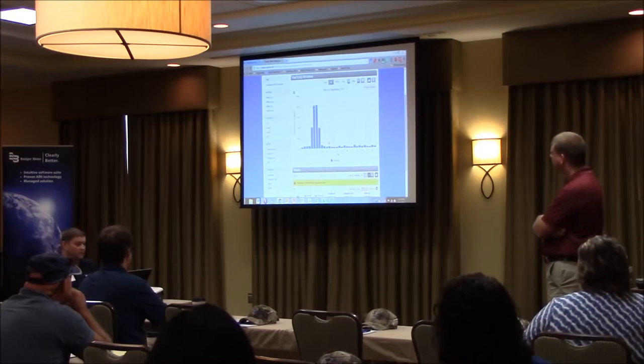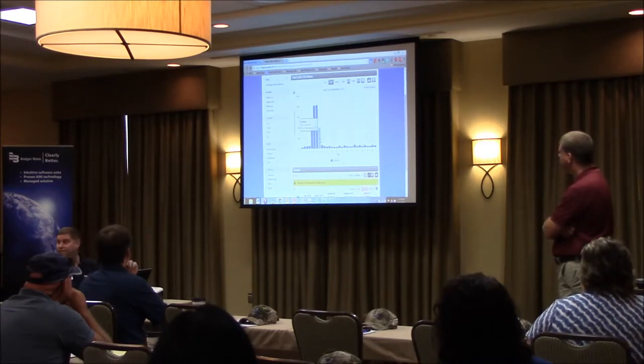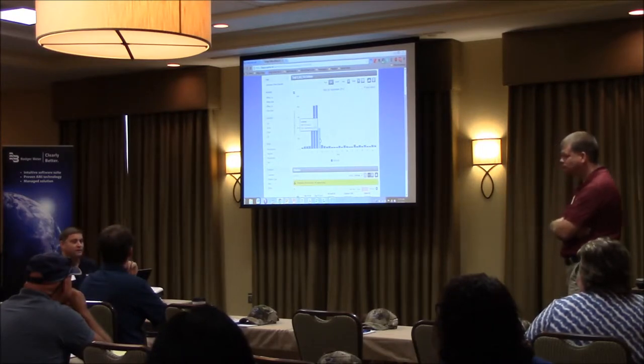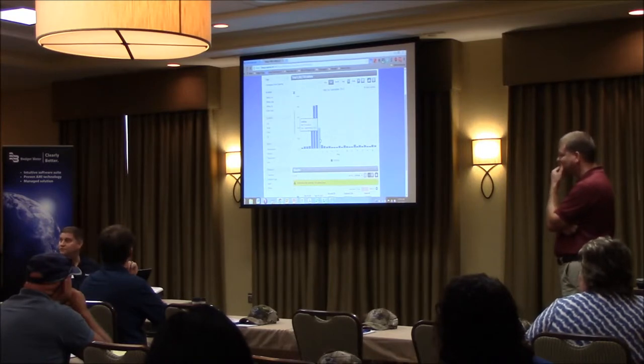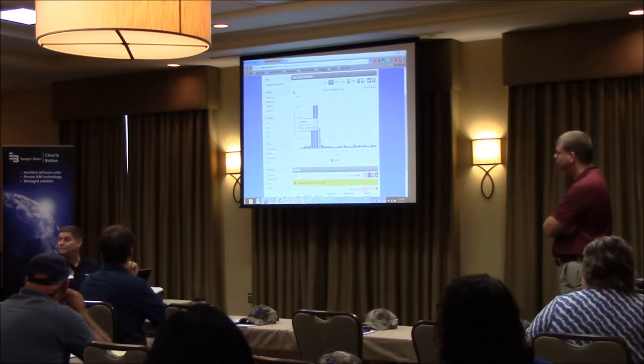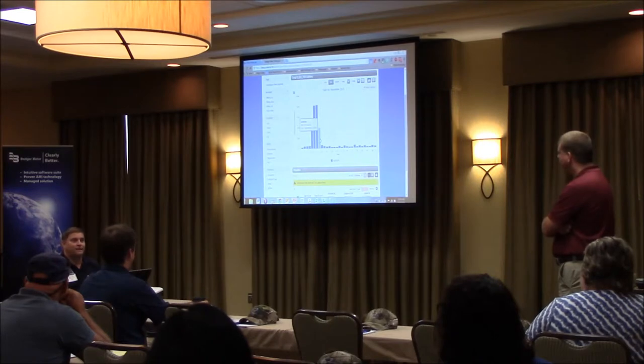I came into work on Monday the 8th, and half my at-a-glance screen was red. The system usage was way up and all kinds of stuff like that. So I started hunting, and in this account, we had run 2.25 million gallons extra through that meter over the weekend. That is a 6-inch service into the sewer plant, and it broke. It was running 500 gallons a minute out.